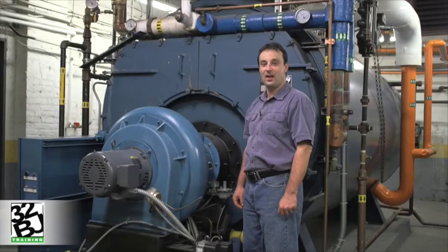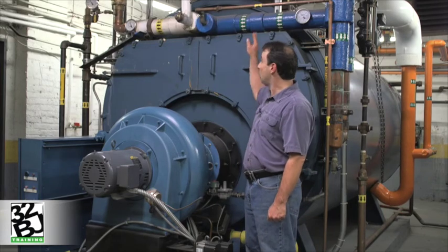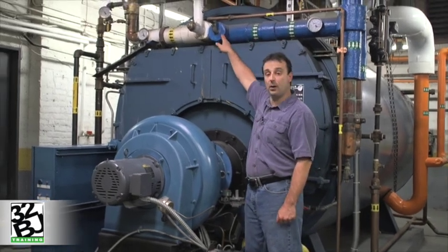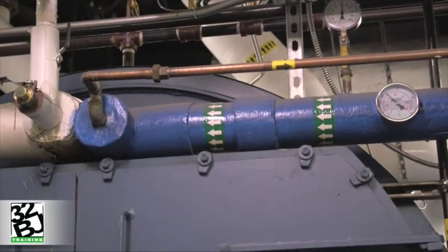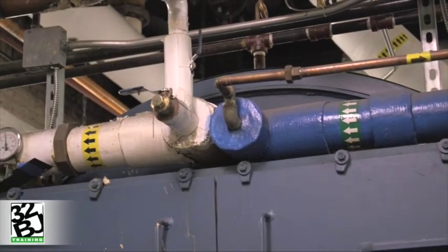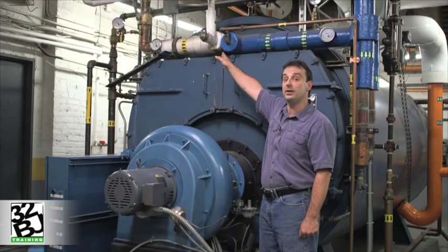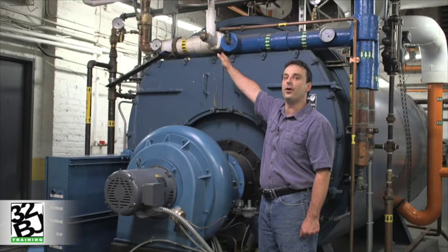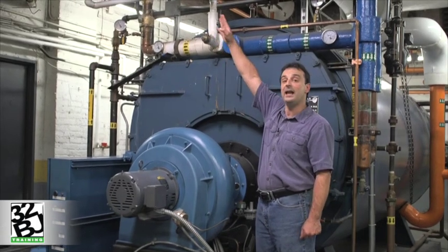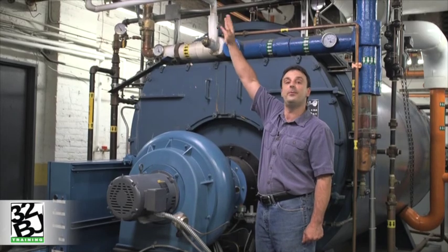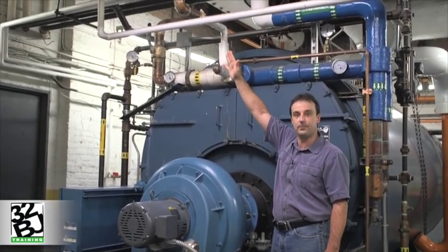As tenants begin to use the domestic hot water in the building, cold water will begin to flow into the hot water coil to be heated by the boiler water. As it exits, this water may reach temperatures of 180 or 190 degrees, which is way too hot for our domestic water. So it exits the boiler and heads on over to what we call the mixing valve, a required component in the tankless system.